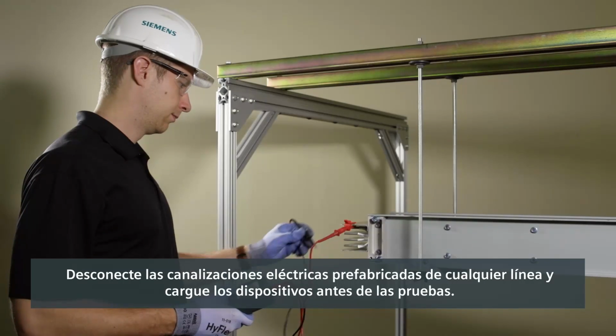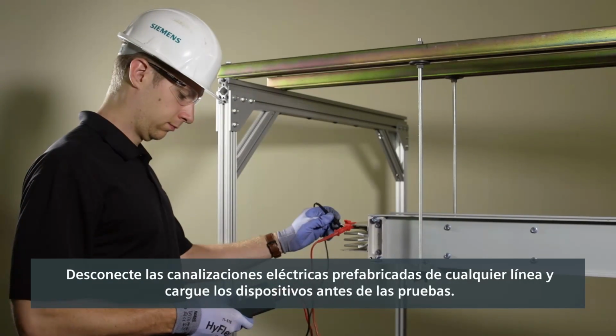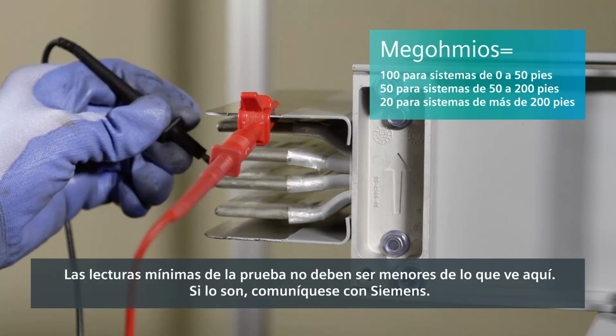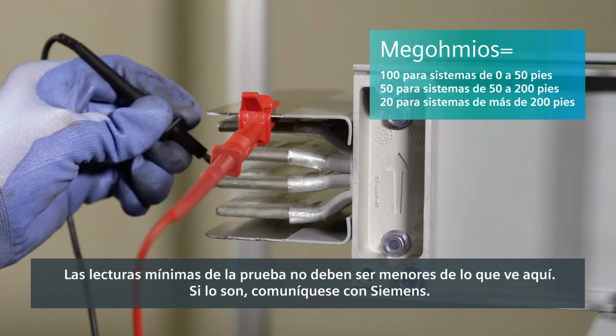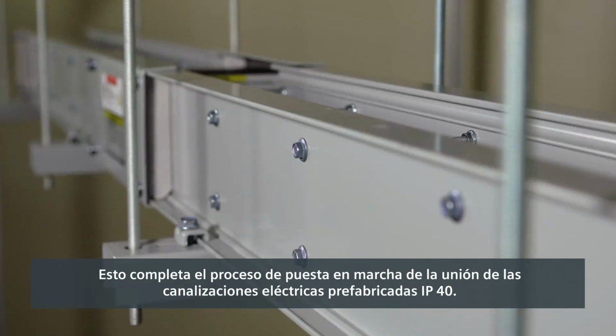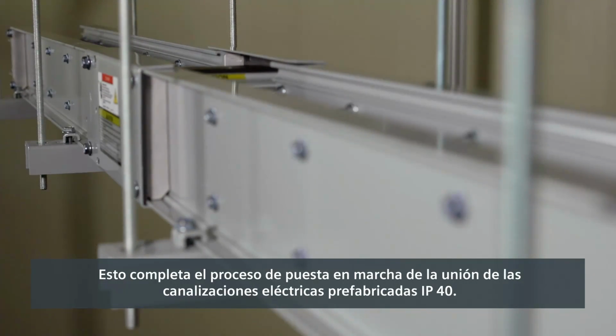Disconnect the busway from any line and load devices before testing. Minimum test readings should not be less than what you see here. If they are, please contact Siemens. This completes the commissioning process of the IP40 busway joint.